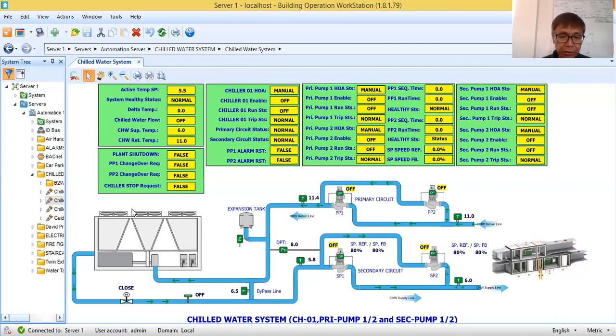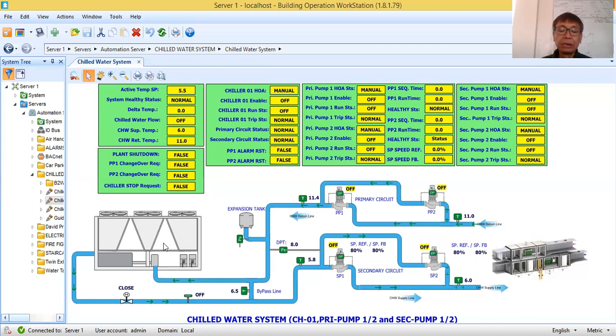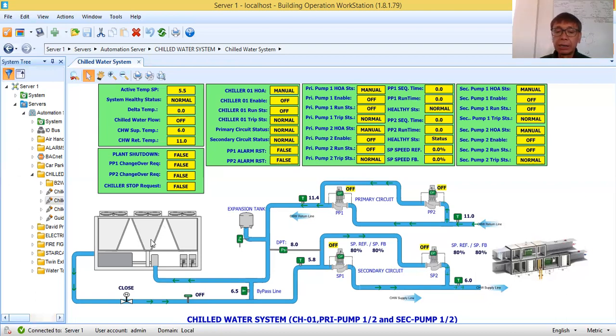The first component of this chilled water system is chiller one. This is an air-cooled chiller with two screw type compressors, one butterfly valve open and close that will be controlled by the building management system, and a start/stop. This chiller has its own control — its own microprocessor-based controller that controls the operation of the chiller.